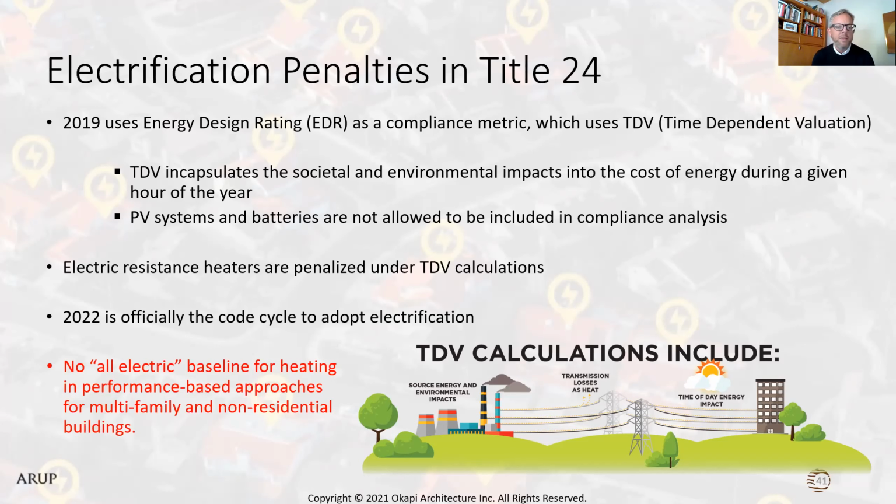And so I think it's important to have that conversation with your electrical and mechanical engineers very early on to come up with an agreed strategy for demonstrating compliance. One of the things that we've done is make the heating system identical between the baseline and the proposed, and then show that the building would comply, and then demonstrate that the proposed electrical system is not worse than that.